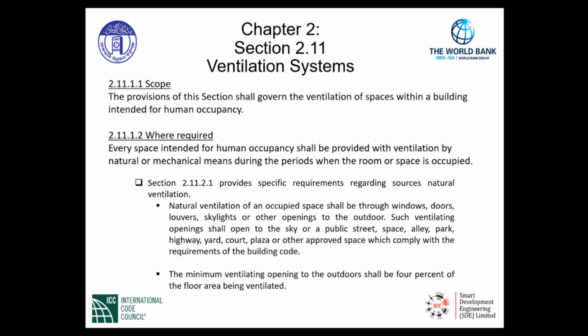When we go to section 2.11.1.1, scope, the provisions of this section shall govern the ventilation of spaces within a building intended for human occupancy. Now, this is where we provide the requirements in the code for ventilation. Where required is given to us in section 2.11.1.2, in that every space intended for human occupancy shall be provided with ventilation by natural or mechanical means during the periods when the room or space is occupied.